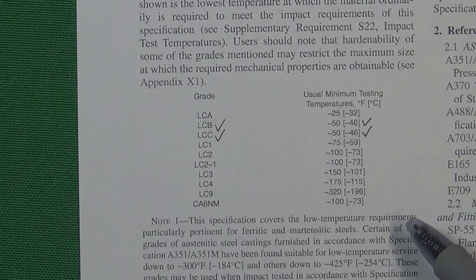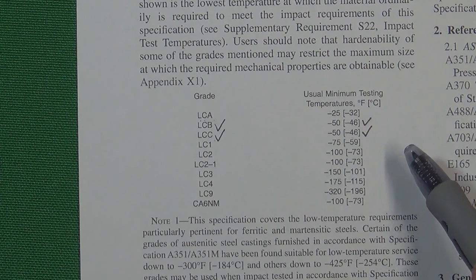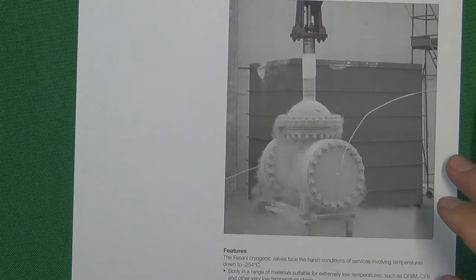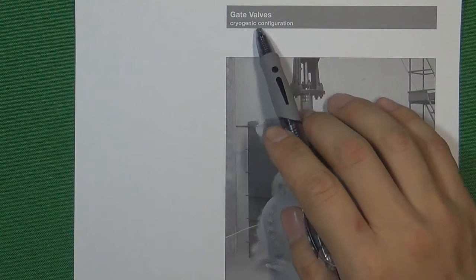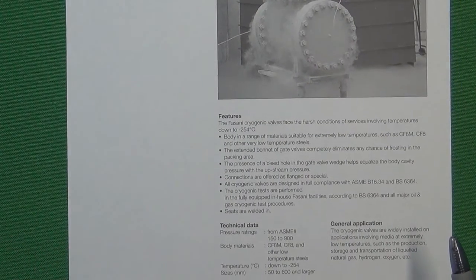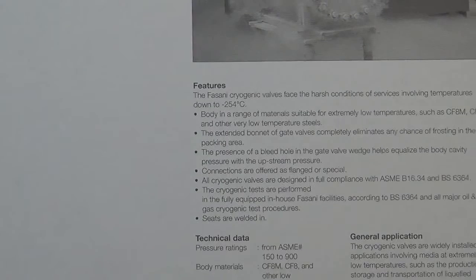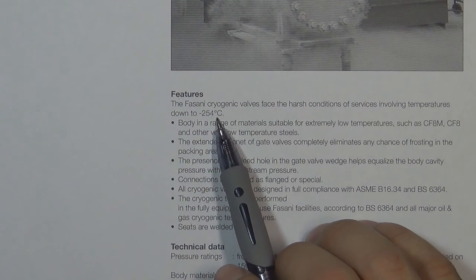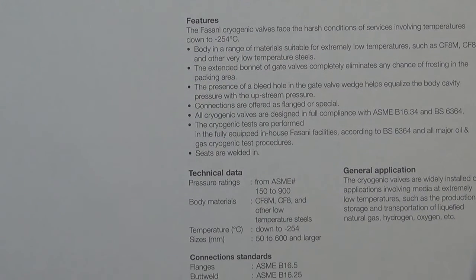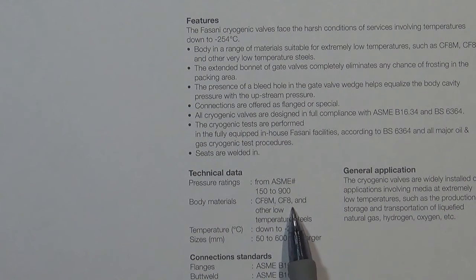So if your flow control system operates at a temperature lower than minus 46 Celsius, what kind of material will be safe? To answer that question, let's look at a catalog here. This is a gate valve manufacturer's catalog offering a cryogenic gate valve. Cryogenic means the flow control system is going to control liquid gas at very low temperatures — according to this catalog, down to minus 254 Celsius degrees. The body material chosen is CF8M and CF8, so stainless steel is the best choice for a really low temperature environment.